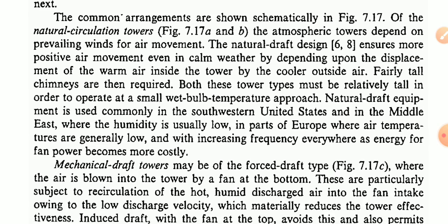Now the common arrangements are shown schematically in Figure 7.17. The natural circulation tower, the atmospheric tower, depends on the prevailing winds for air movement. The natural draft design ensures more positive air movement even in calm weather by depending upon the displacement of the warm air inside the tower by the cooler outside air; fairly tall chimneys are required. Both these tower types must be relatively tall in order to operate at a small wet-bulb temperature.